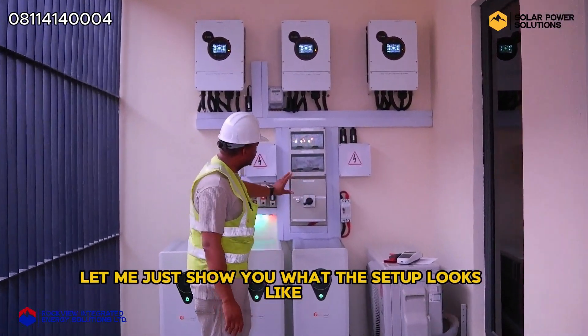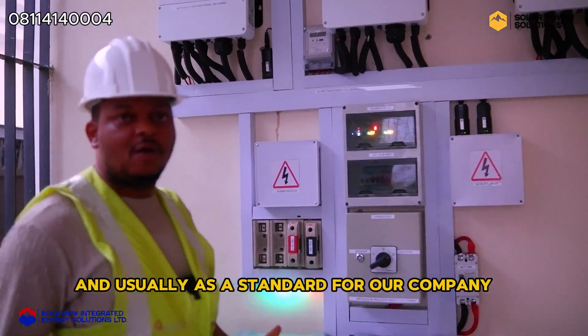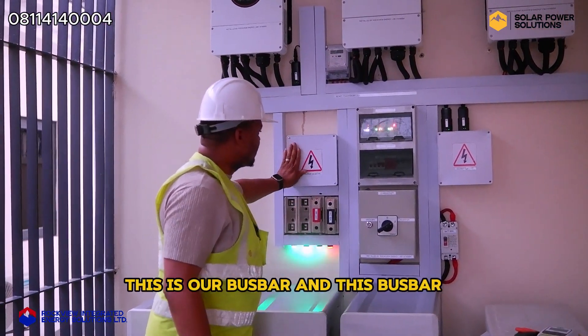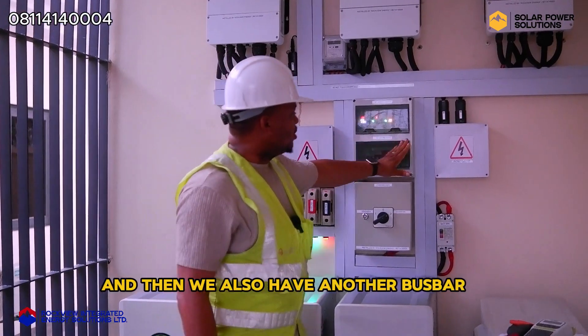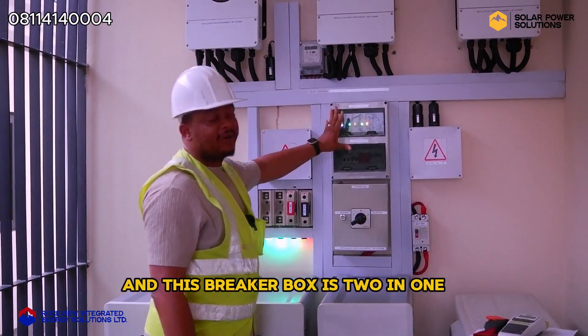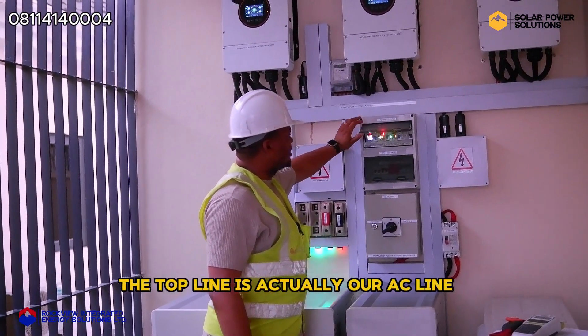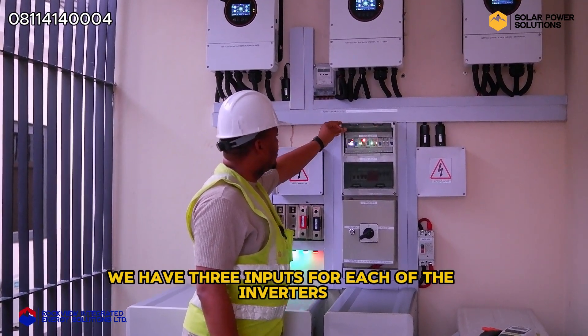If you come closer, let me just show you what the setup looks like. Right here we have a breaker box, and as a standard for our company we usually label our installation so that one can actually understand what the setup looks like. Right here is our bus bar — this bus bar handles the negative terminal, and then we also have another bus bar which handles the positive terminal. Right here is our breaker box, which is two-in-one handling our AC line and our DC line. The top line is actually our AC line, and as you can see we have three inputs for each of the inverters.